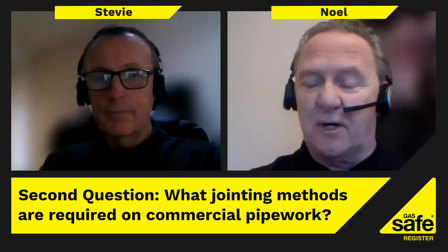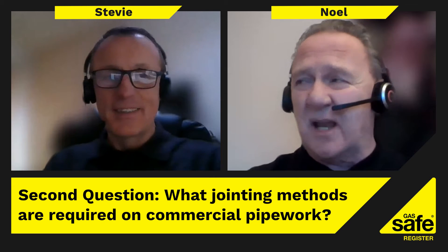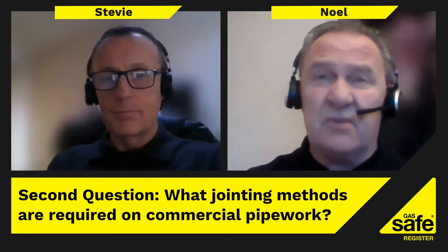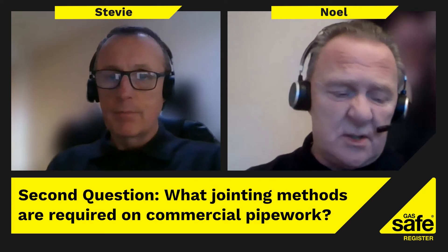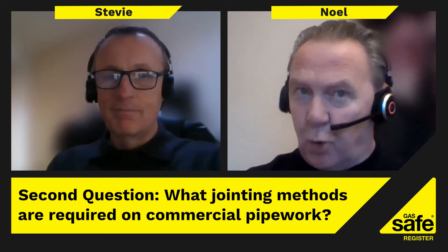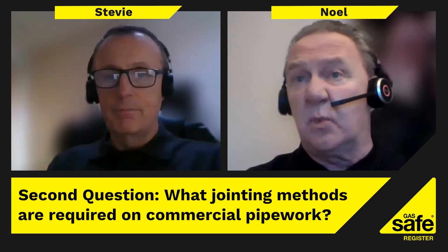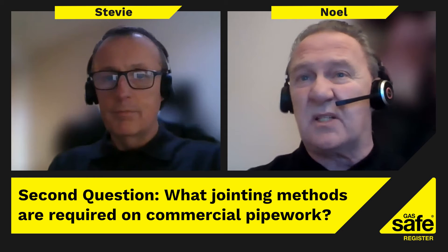Copper must be correctly jointed and should not leak throughout its lifetime under normal conditions, however local environment and mechanical damage can have an impact on that. Joints should be accessible and joints should not be located in sleeves, other than those that are welded or brazed. Joints shall not be located such that air movement alone would dilute minor leakage - ventilation wouldn't necessarily cope with a catastrophic failure. A non-metallic pipe must not be used within the building except for entry.